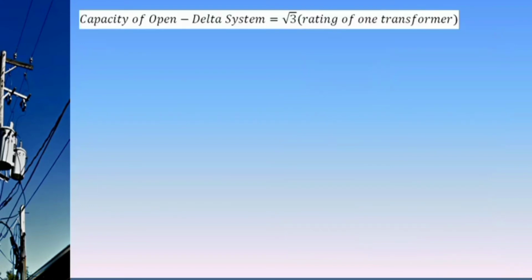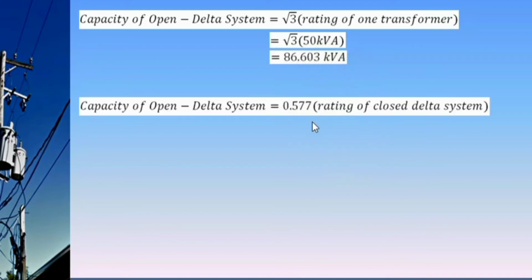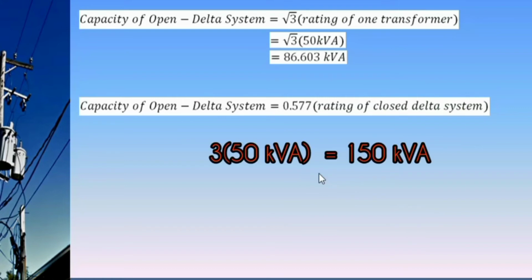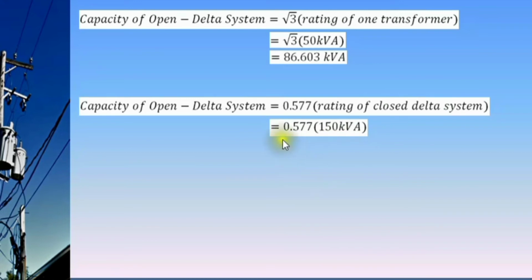Let's have another example. What if we have an open delta system that uses two transformers, each having 50 kVA rating? Substitute 50 kVA to this equation. We have square root of 3 times 50 kVA. This will give us 86.603 kVA. If we multiply 0.577 to the rating of the closed delta system, where we have 3 times 50 kVA, that will give us 150 kVA. Multiply that by 0.577, this will give us 86.55 kVA.